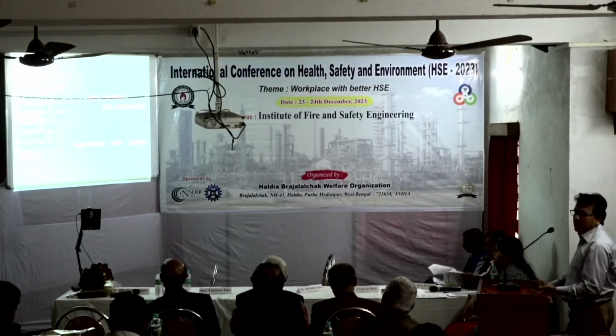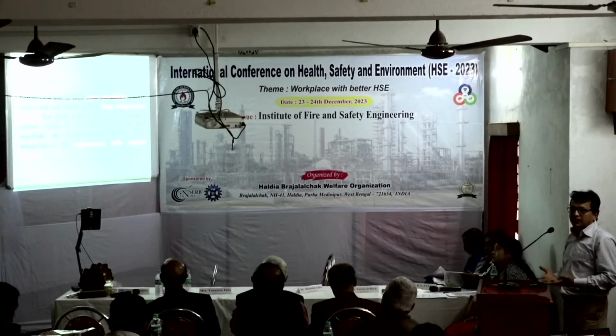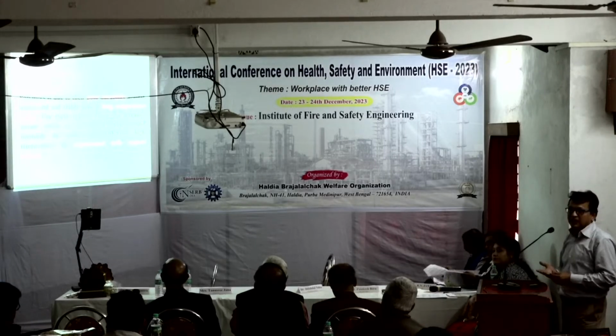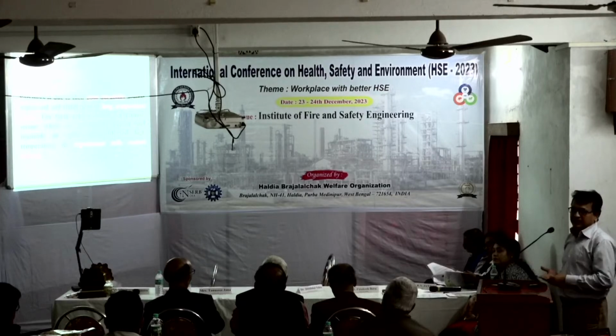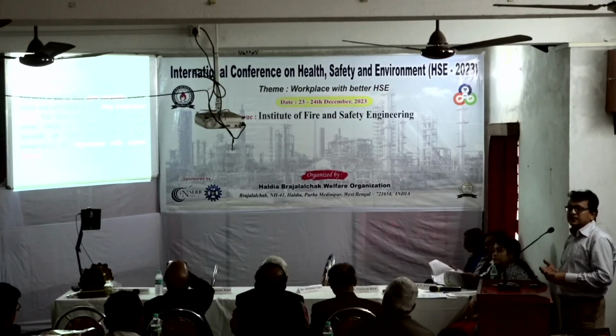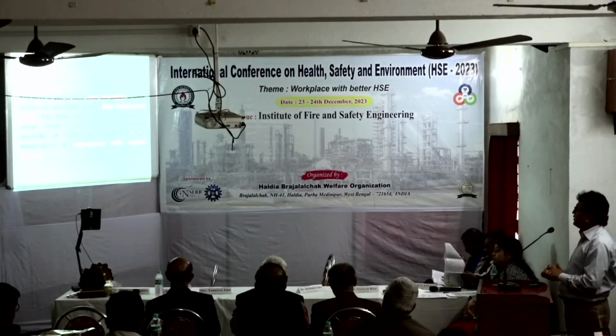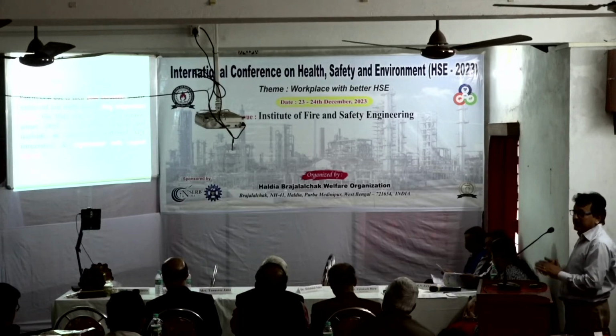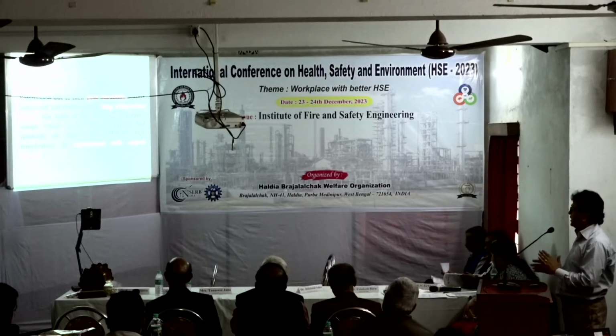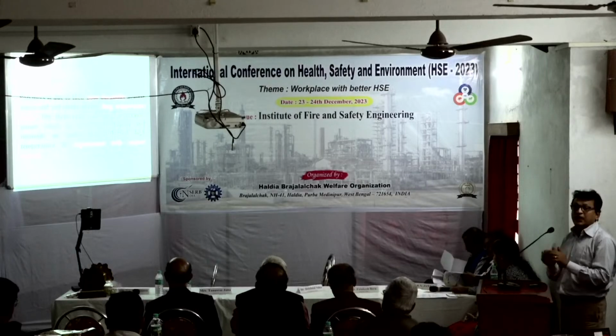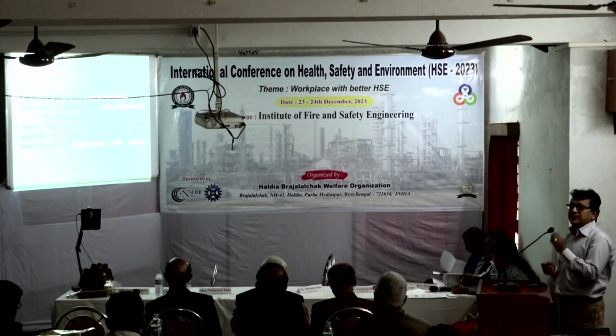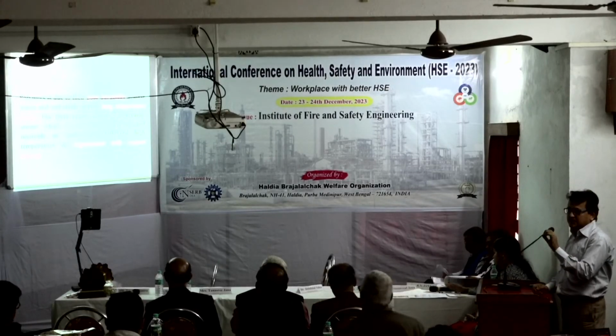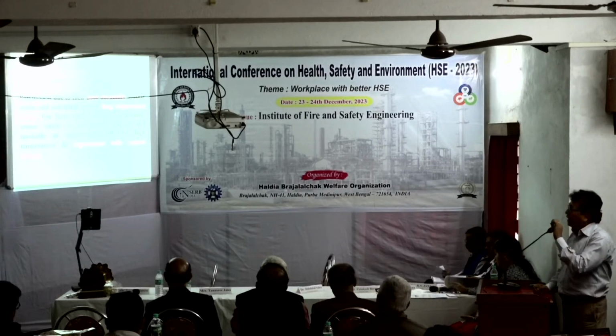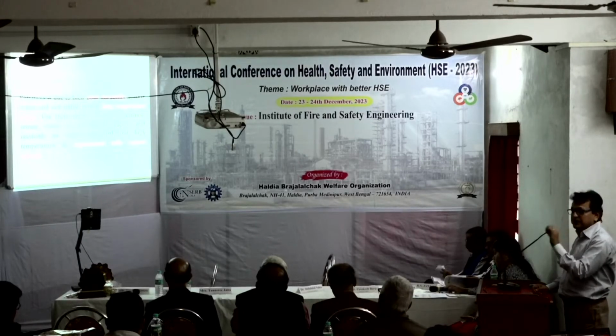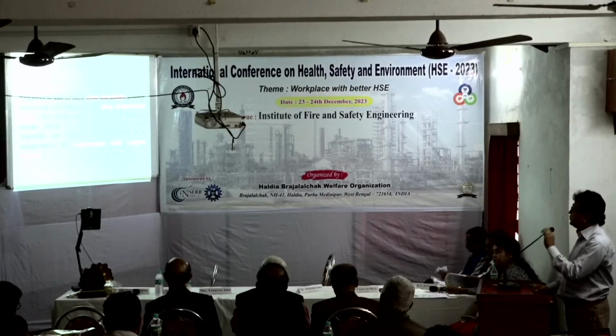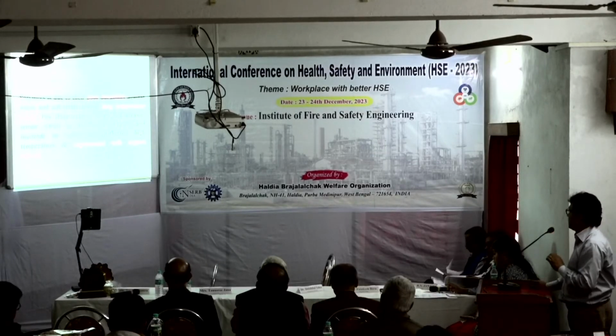So the question is, why ceramic, why not polymer? Polymer has two difficulties: first, it easily degrades, and second is temperature stability. Polymer materials cannot remain stable above 50 degrees centigrade, but there are special applications requiring temperatures above 100 or even 200 degrees centigrade. In those temperature regions, moisture sensors are required, and there is no option to use a polymer sensor. A special ceramic based sensor is required, that is why we work on ceramic based sensors.